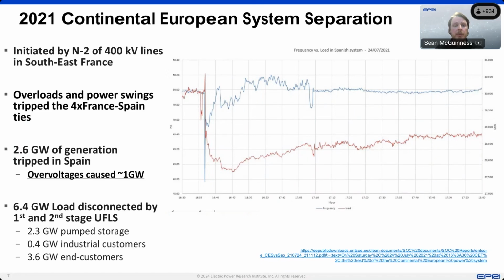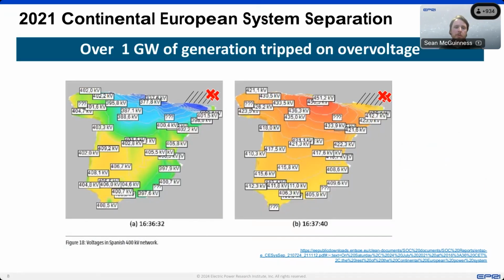Now, the reason for the overvoltages was that initially when the first two 400 kV lines tripped, this resulted in a loss of megavars and a decline in voltage in the northeast of Spain. So you can see from these two charts here on the top left, this shows the voltage profile on the 400 kV grid immediately after those two lines tripped. So you can see that for a nominal voltage of 400 kV, parts of the grid were as low as 377 kV, so it was quite well down. So this persisted. This wasn't a transient dip; it was sustained.